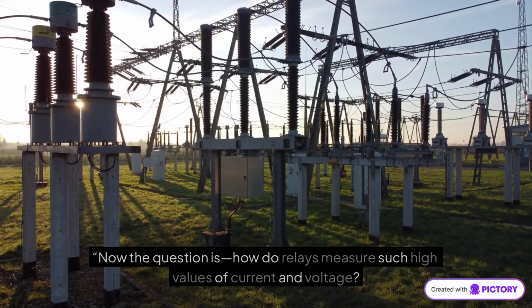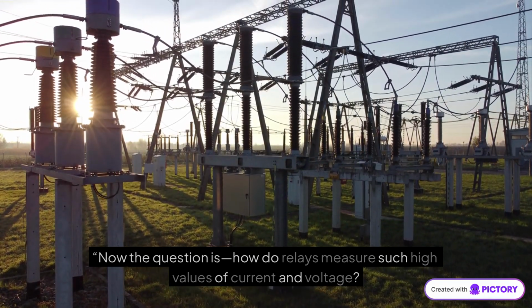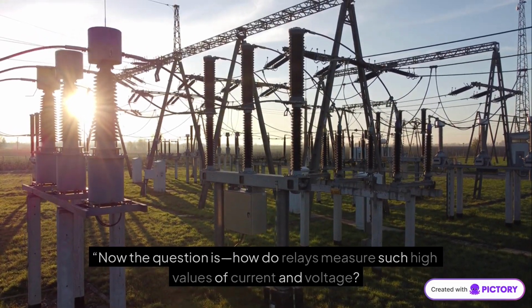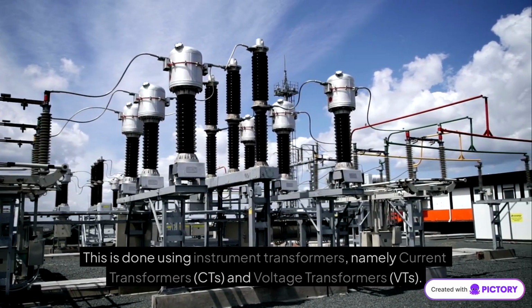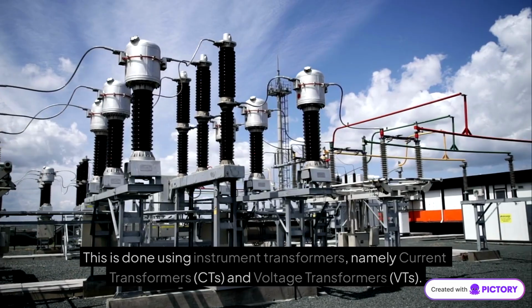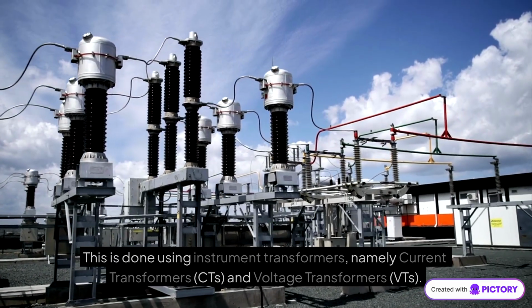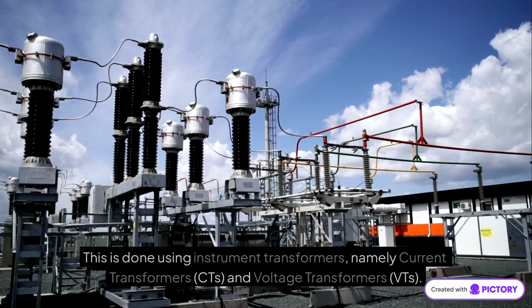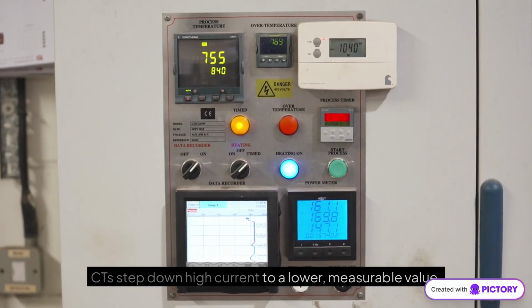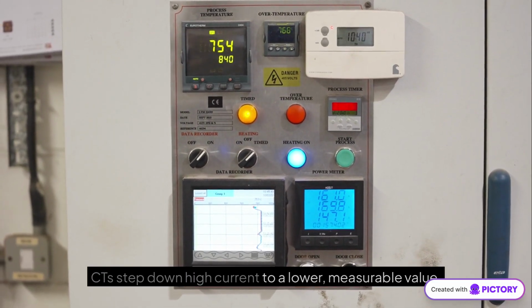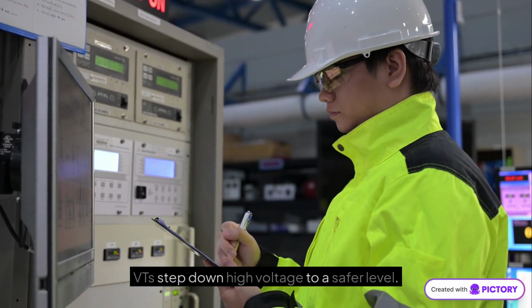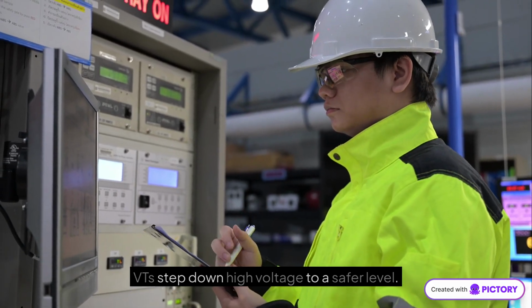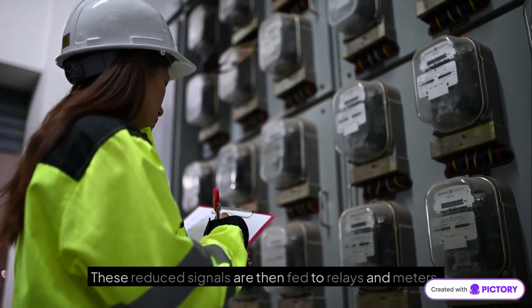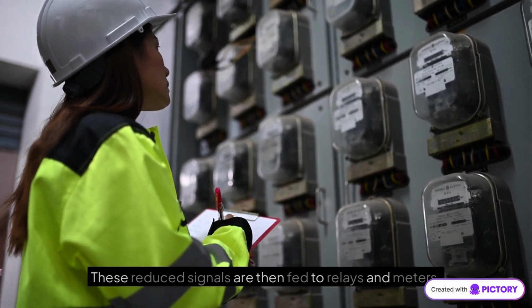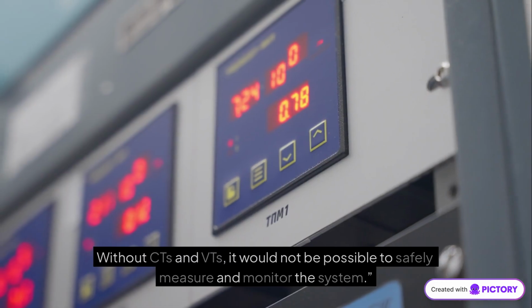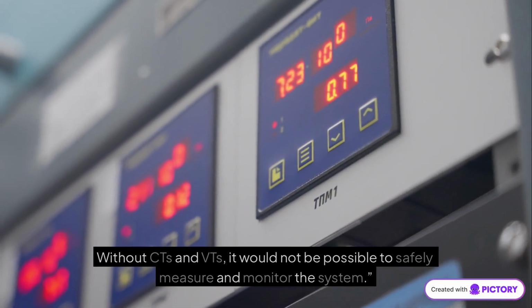Now the question is, how do relays measure such high values of current and voltage? This is done using instrument transformers, namely current transformers, CTs, and voltage transformers, VTs. CTs step down high current to a lower, measurable value. VTs step down high voltage to a safer level. These reduced signals are then fed to relays and meters. Without CTs and VTs, it would not be possible to safely measure and monitor the system.